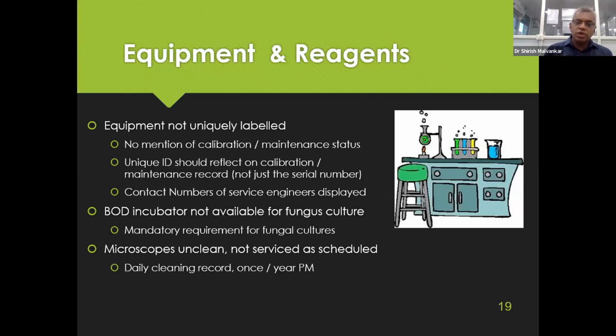Contact numbers of service engineers may be displayed on the side of the instrument. This is for junior staff. If they are working in late shift, they should know whom to contact in case of any breakdown. If you want to include mycology in the scope, you need to have a BOD incubator available. It is a requirement as per NABL 112 for fungal cultures.